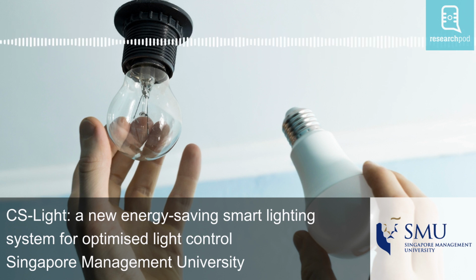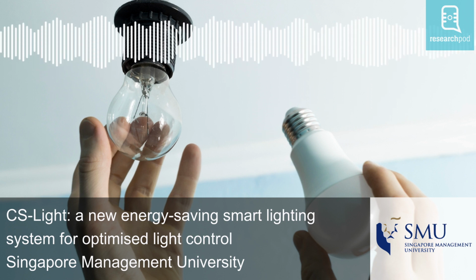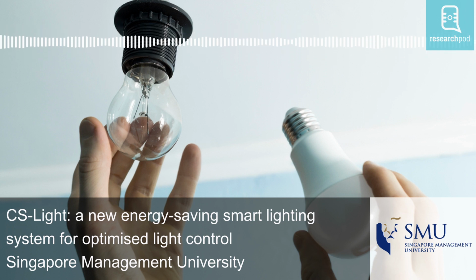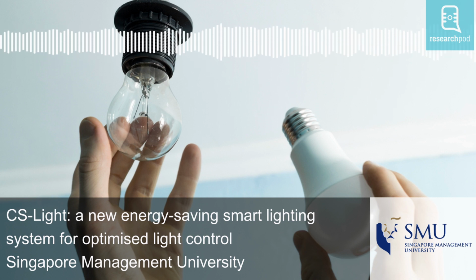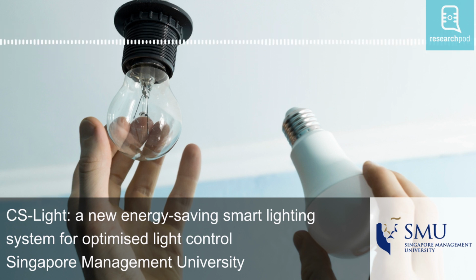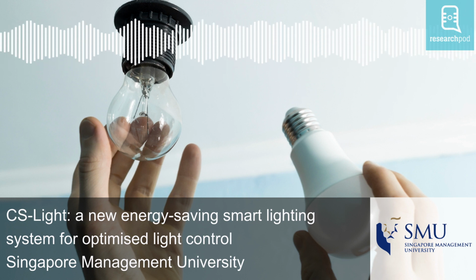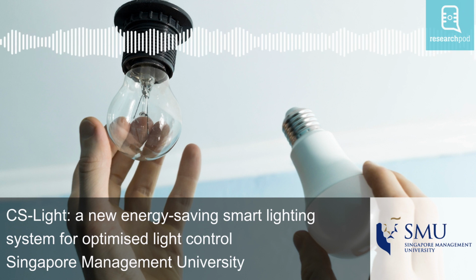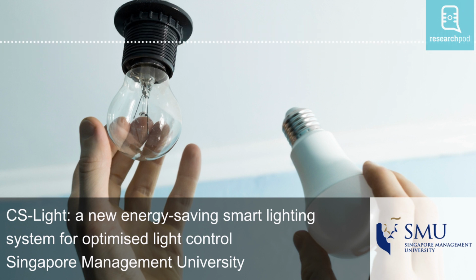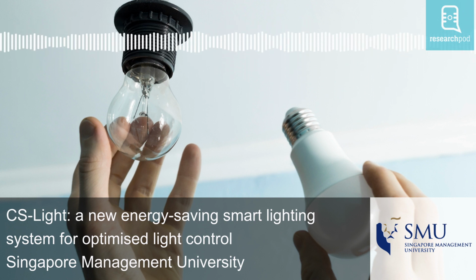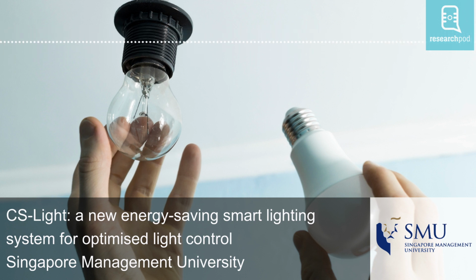Coarse-grained lighting control groups multiple light fixtures together and controls them as a single unit, rather than controlling each fixture individually. In an open-plan office, where occupancy may be high in one area and low in another, motion sensors may pick up low occupancy in this instance and dim all lights because they are linked together as a single unit. Or else, if the occupancy sensor senses high occupancy, it will brighten the LEDs throughout the space, potentially illuminating even unoccupied tables or pods needlessly.